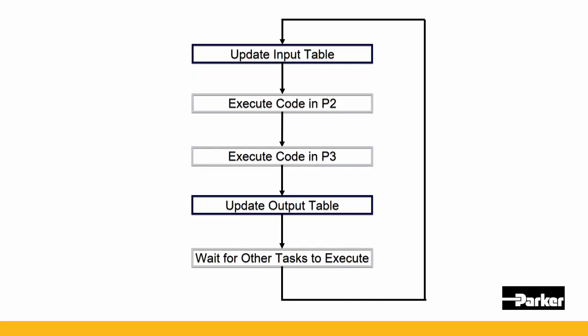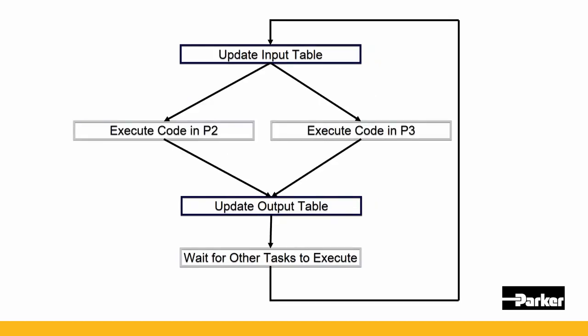In other words, their logic is executing based upon the same input state regardless of the other code that has been executed in that same task. If you struggle with this concept, the best way to think of it is that the POUs in a single task execute at the same time and they do not affect one another until the next scan.